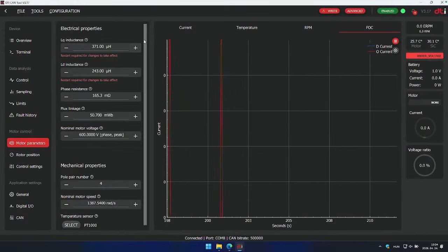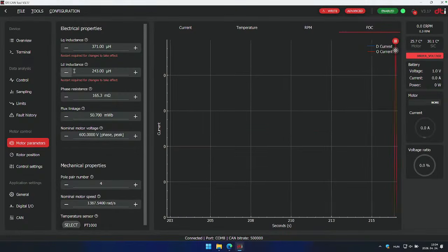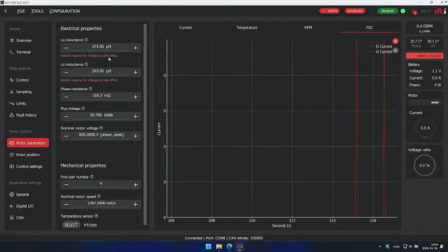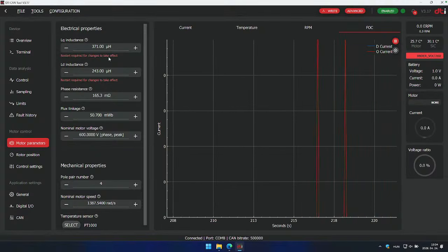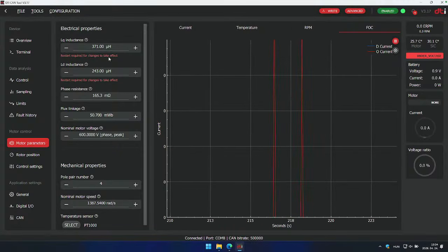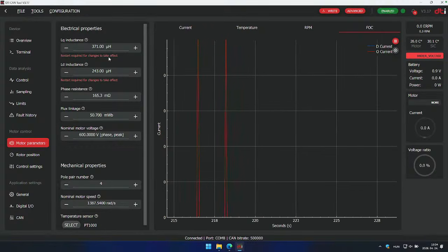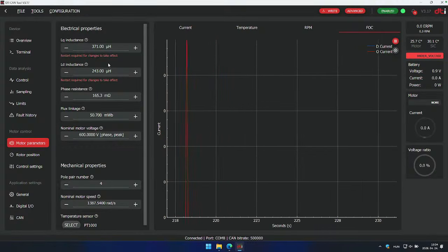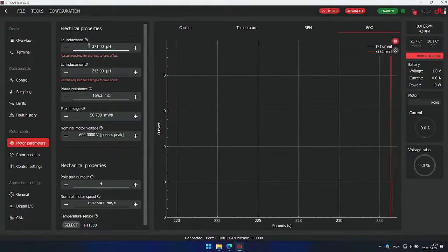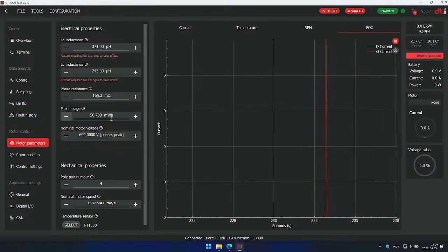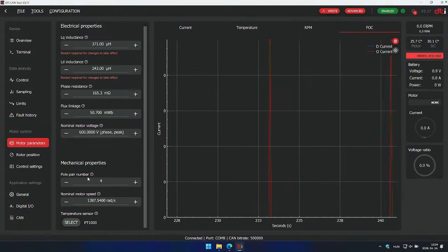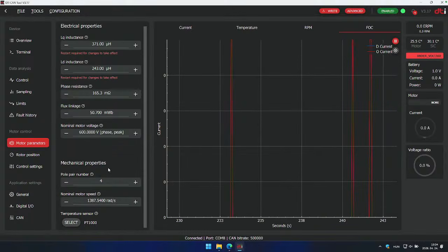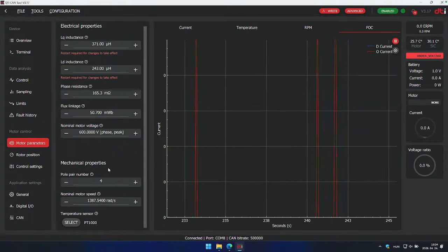Motor parameters are the most crucial parameters here. The LQ and LD inductance are responsible for computing the PI current controller gains, and these parameters, for the DTI F motors, are validated and tested on our dyno. Also the phase resistance, flux linkage, and nominal motor voltage. By default you get this data and can trust it.